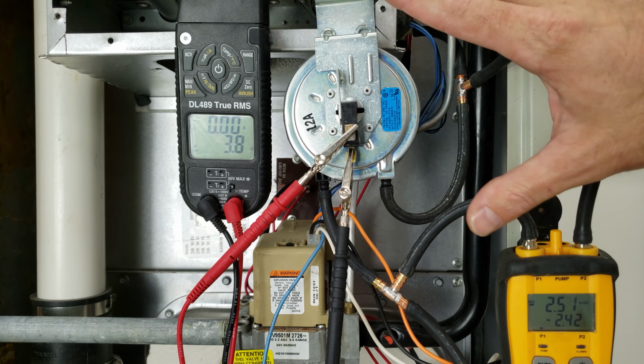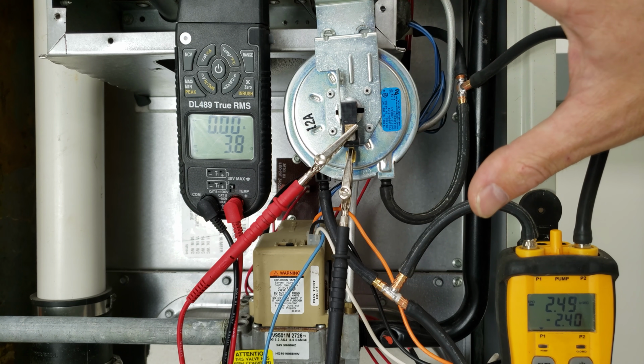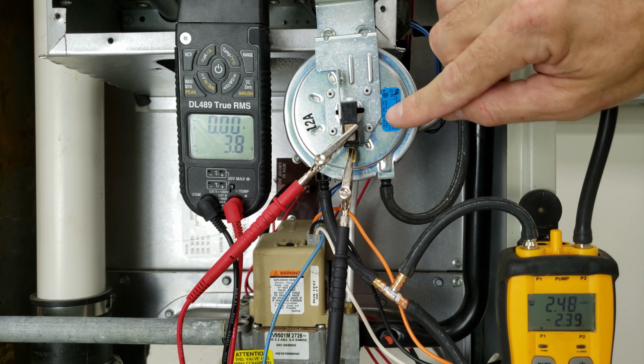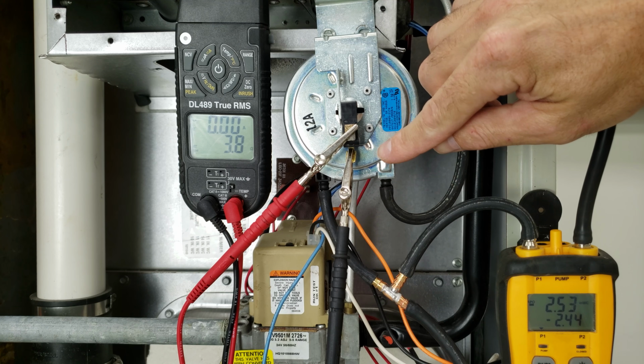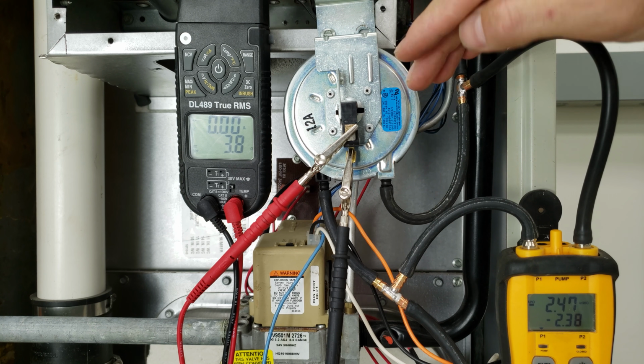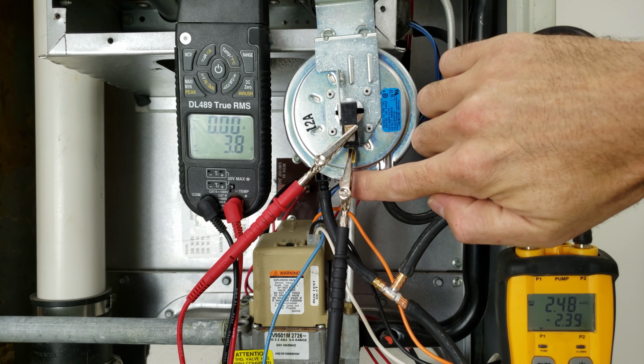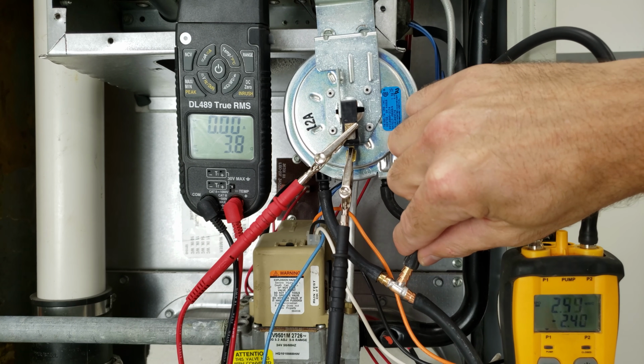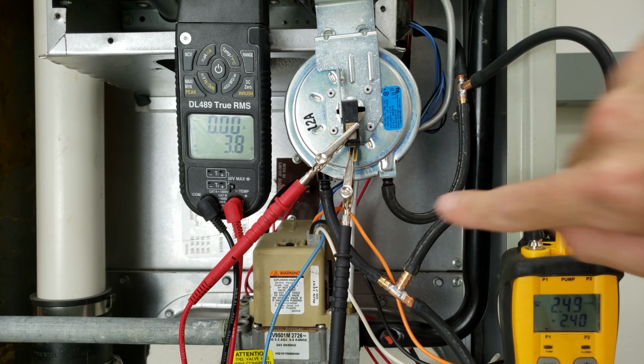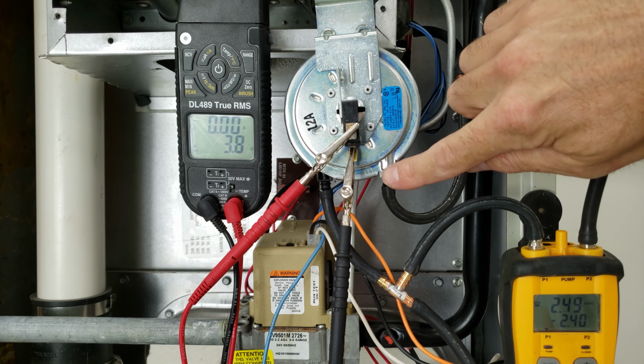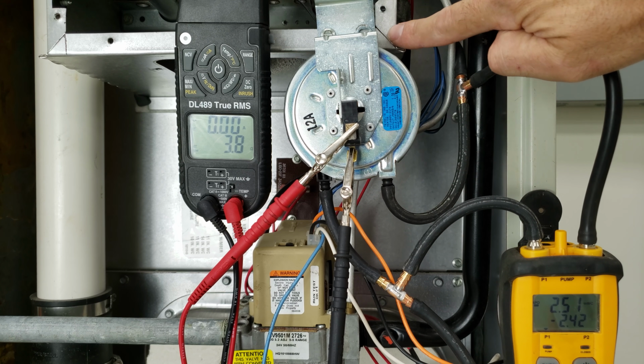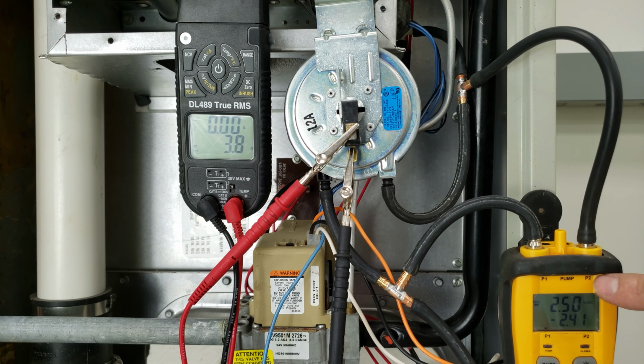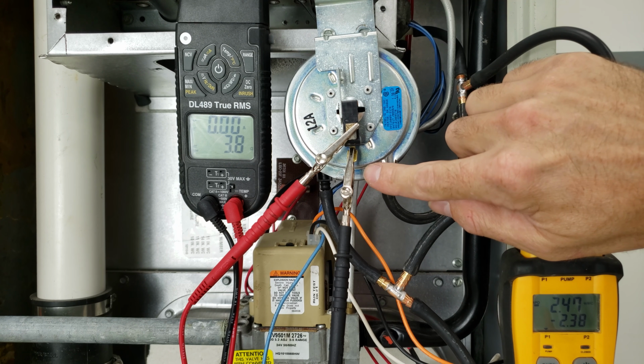So we have our inducer motor running right now, and we have a call for heat, but we have our electrical wires off of the pressure switch, so that's why it's continuing to run. We have our negative port right here connected to our pressure switch and teed in, and that's on P1. And then we have our positive port connected to the combustion chamber, and that's teed in on P2. So on P1, we're measuring 2.49 inches of water column. That's the pressure reduction on that side of the pressure switch.